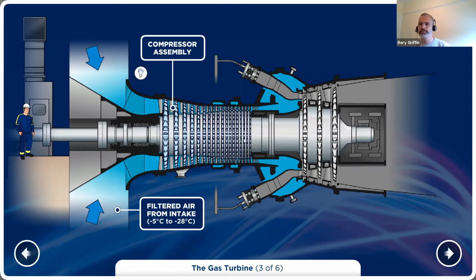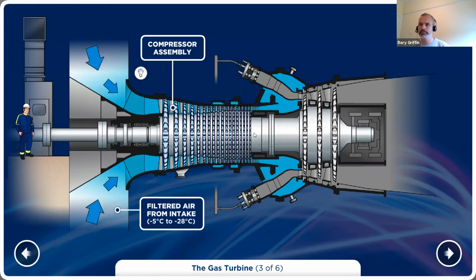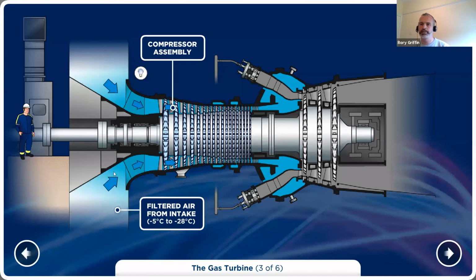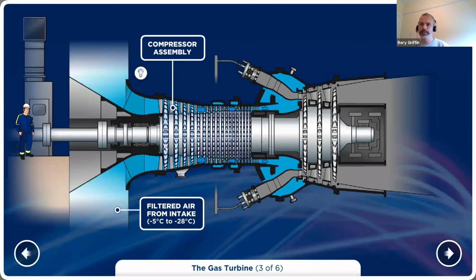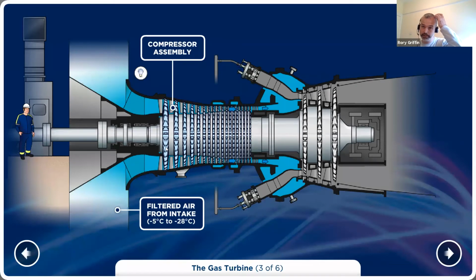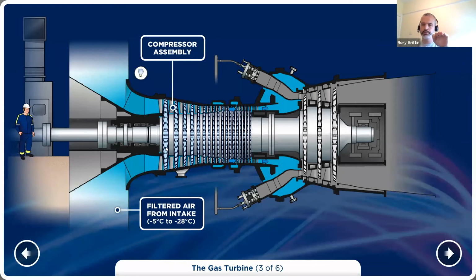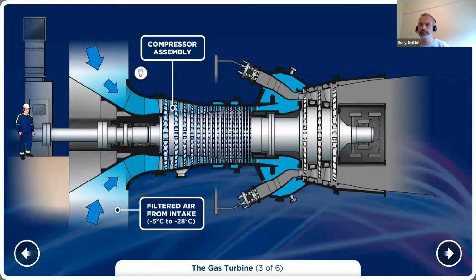there's 18 rows of blades. So the number of stages of blades will give you an idea of what level of compression you'll get on the air. So it comes in at atmospheric pressure, maybe just a little bit down from it because of coming through the filters, and it gets squeezed then through each row of blades. So each blade, there's a lot of analogies here with an aircraft. There's an airfoil shape on the cross section. So this is designed to catch the air coming in. You get a downward force, which will start to turn the shaft of the machine. The last thing you want in a compressor is any kind of turbulent flow of air.